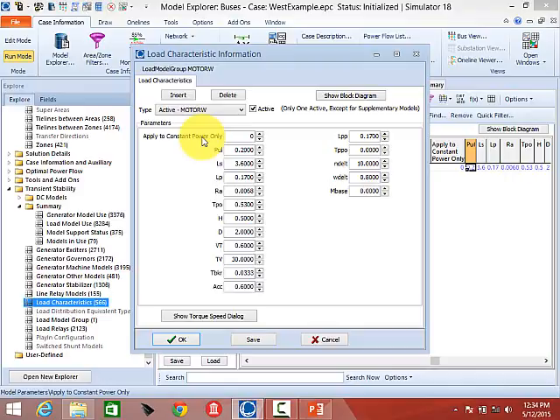Question: did all this data come from the example DYD file? Yes — all this dynamic data was loaded by that DYD file. There's no default data in here; it's just what was in that file. The EPC file didn't contribute dynamic data — it only provided bus numbers, bus names, and power flow model setup. So the EPC file said 30 megawatts and 15 megavars at a bus, but how that load or generator should be dynamically modeled came out of the DYD.